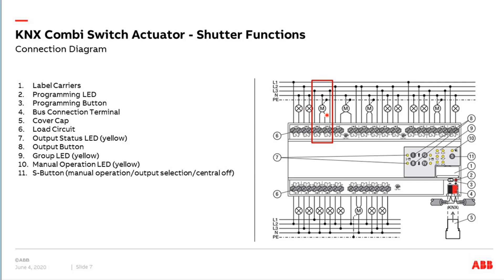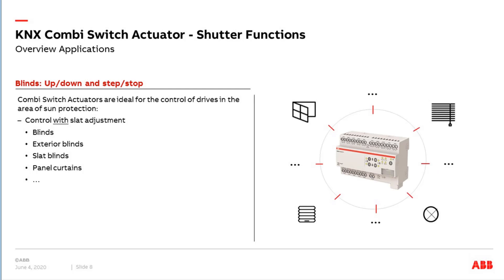The connection diagram shows a mixture of lamps but also motors, shutter appliances, curtains, and more. We need two relay outputs to control a motor — for open/close, up and down. Different from classical shutter actuators, we have no change-over contact but two independent relays operated like a change-over contact via software. So a shutter channel uses two outputs, meaning a 24-fold CombiSwitch Actuator becomes a 12-fold actuator for shutter functions.